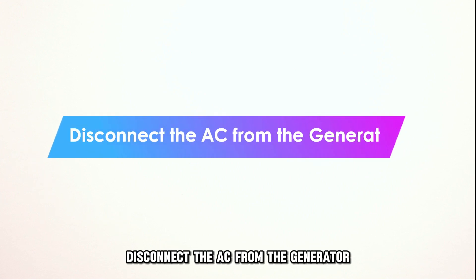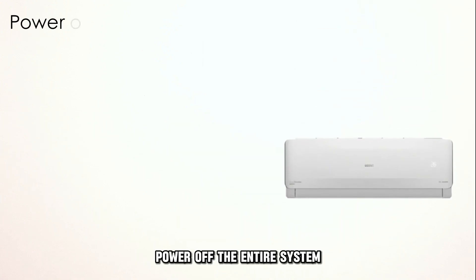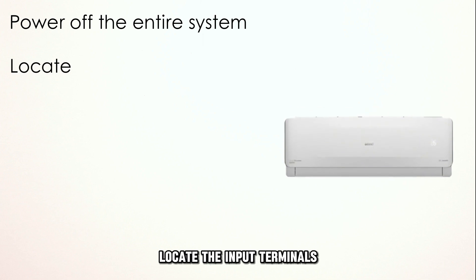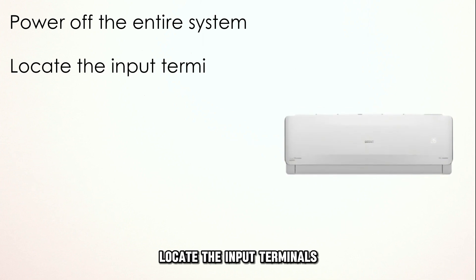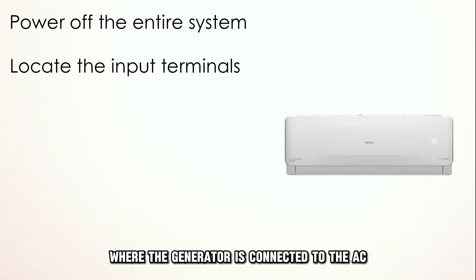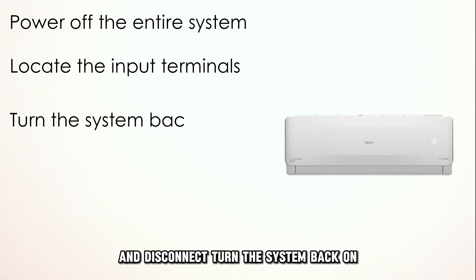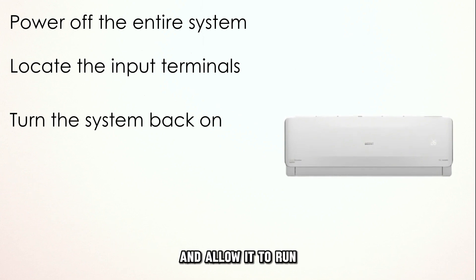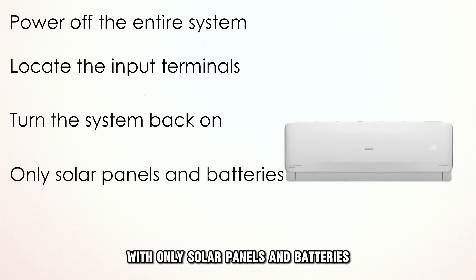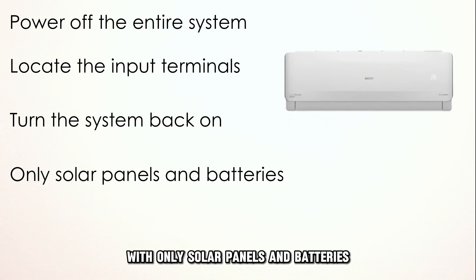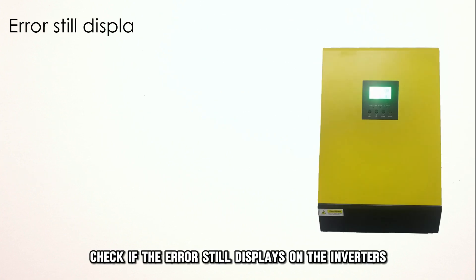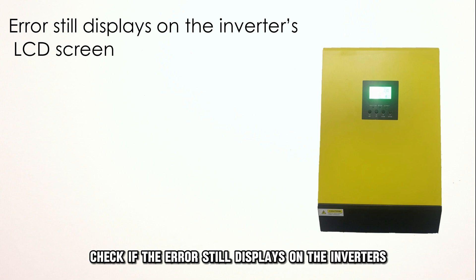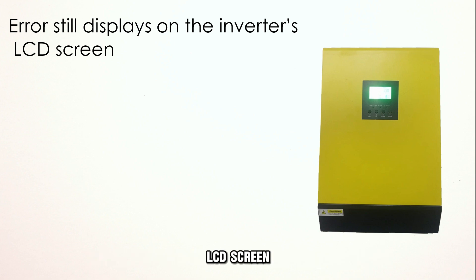Disconnect the AC from the generator and power off the entire system. Locate the input terminals where the generator is connected to the AC and disconnect. Turn the system back on and allow it to run with only solar panels and batteries, then check if the error still displays on the inverter's LCD screen.